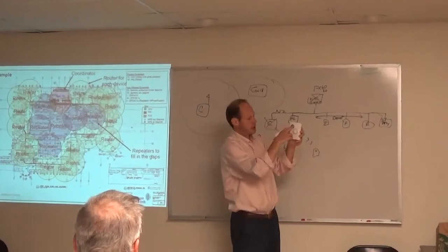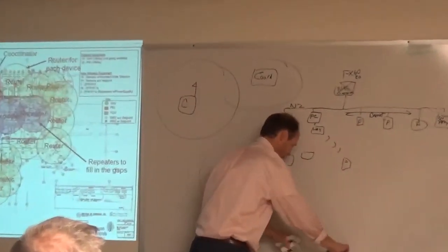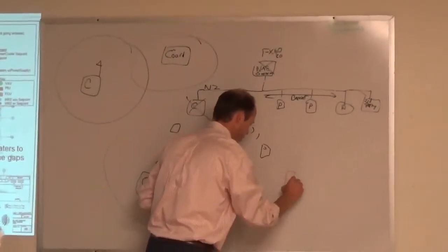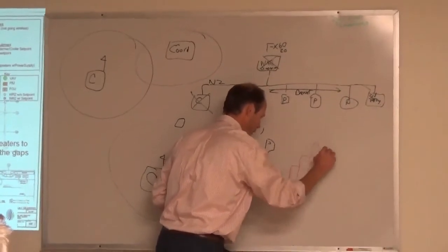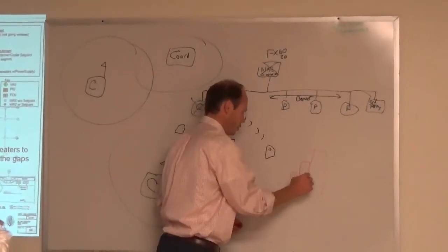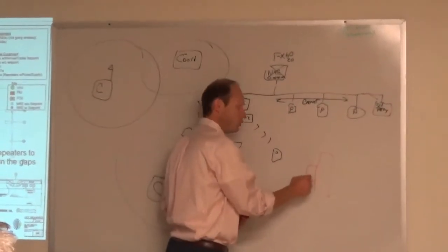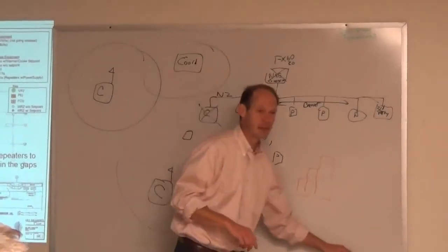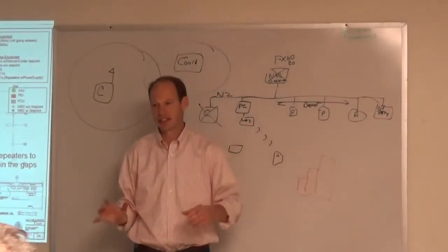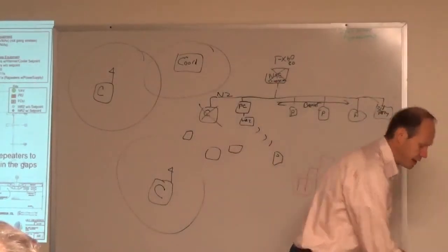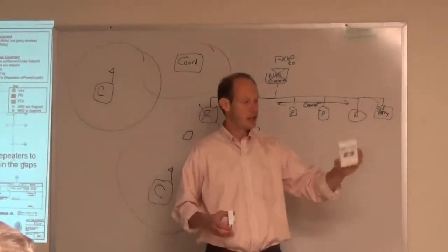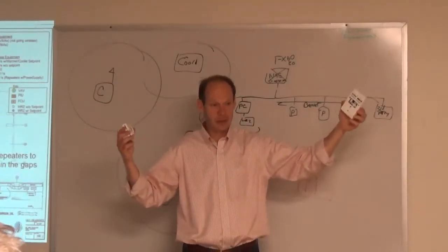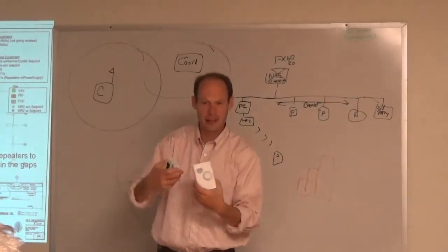If I get on these guys, the display will show like a graduated scale. It shows like this. You know, one, two, three. So if you have one, two, three, I've got great communication. If you've got two, it's still okay. If you've got one, you might have a tendency for something in the way, like an elevator shaft, where the signal is attenuated somewhat. So if I'm sitting here, I can put the sensor in the room next door, hit the button and see, do I have communication between them? If you have no display, it's just a little LED on there, one, two, or three blinks.